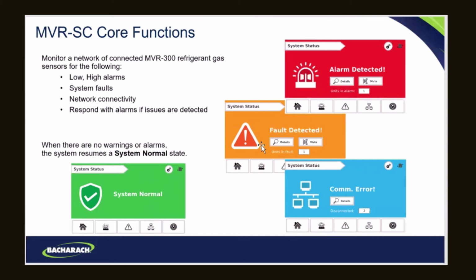Same thing happens if there's a fault detected. You'll be able to mute the alarm. You'll be able to see what the details are, and you'll be able to figure out where that MVR-300 is located. Same thing with a communication error. So all three of those system events are typically what happen, and the controller logs them and tracks them and will tell you exactly where they are.